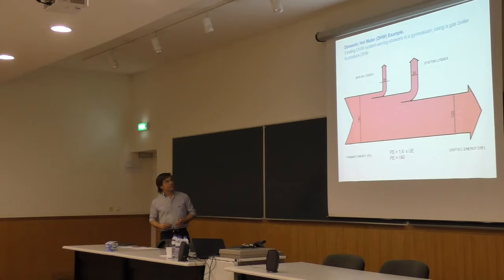And then we have system losses, and I will explain what these system losses are. In hot water systems in buildings, system losses are huge. Most existing buildings have hot water systems that are dramatically inefficient, and I will say why. Again, we have the boiler losses, the system losses, and then we have the final useful energy for the showers. Okay? And so this equation shows that primary energy is 1.4 times the final useful energy in this system.